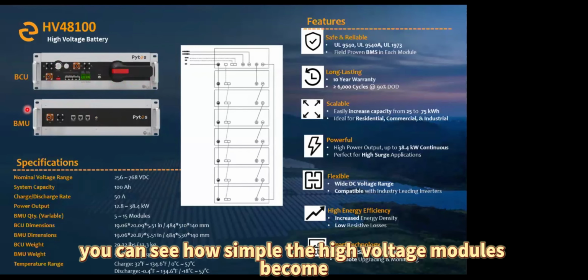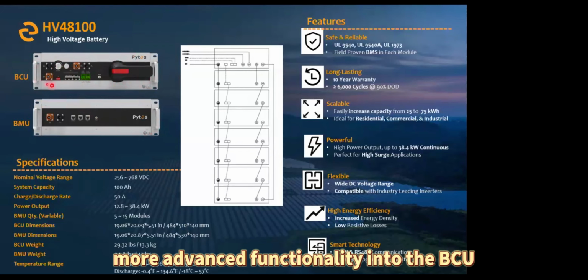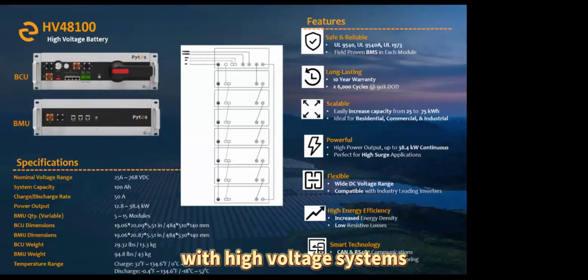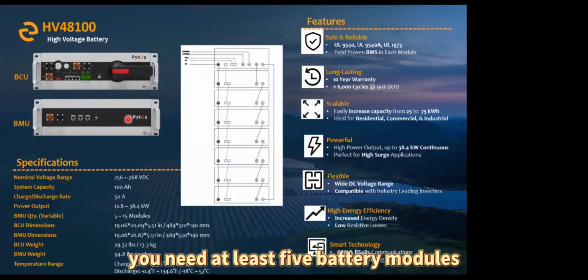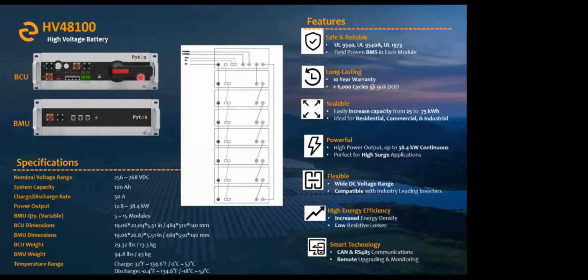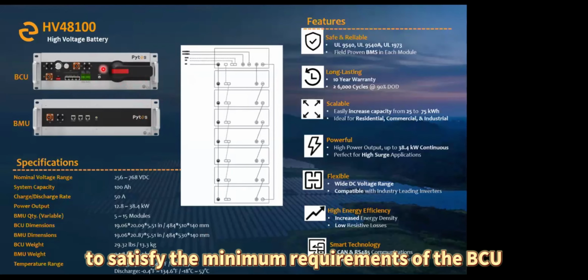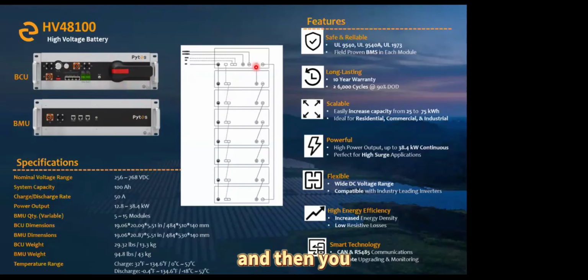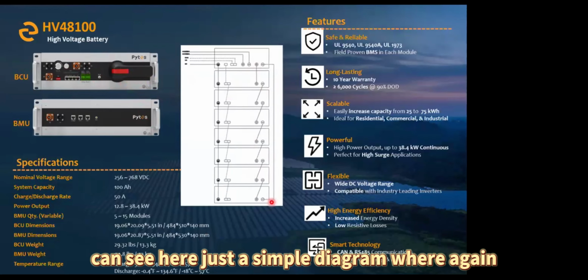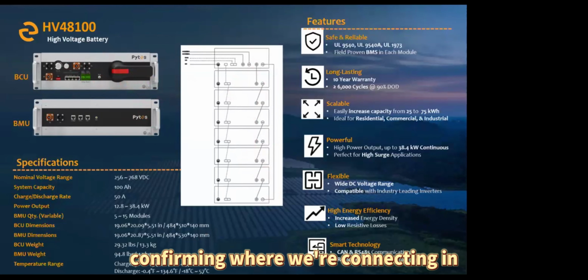You can see how simple the high voltage modules become now that we've built all that more advanced functionality into the BCU. Part of the reason is that with high voltage systems, you typically need more than just one battery for a fully functioning system. With our setup, you need at least 5 battery modules, 25 kilowatt hours, to satisfy the minimum requirements of the BCU. Here's a simple diagram confirming we're connecting in series, not in parallel.